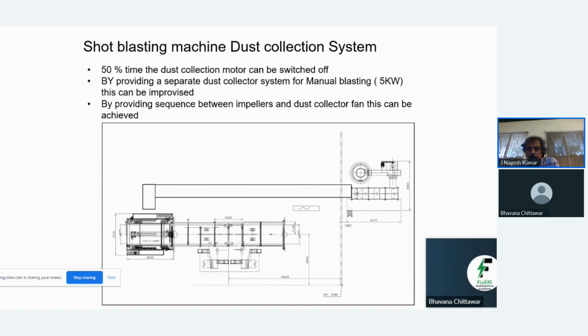But this fan is continuously in operation. It's a huge fan. Once the shot blasting starts, the motors start and the dust generation happens, but the fan is continuously rotating. It's a 180 kilowatt fan. The company has a soft starter for this fan. What we have done is to interlock the shot blasting motor with this fan, so that only when the shot blasting starts, this motor will start. As a result, this fan's operation came down by 50%. There is no need for this fan to operate continuously. There's one more manual blasting booth which is also connected to this.